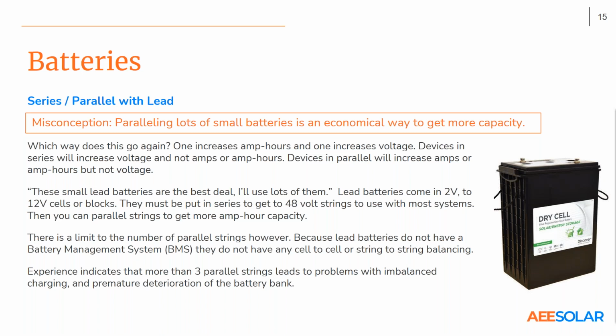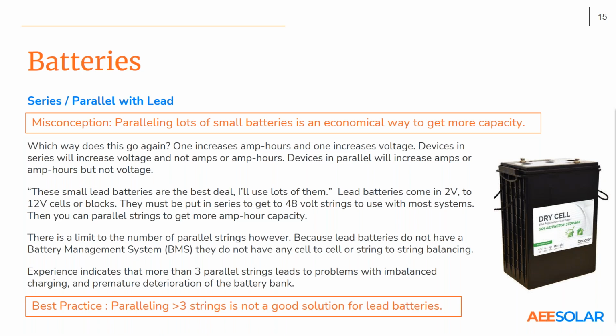So the rule of thumb is that with a lead battery, because they don't have a battery management system to do this balancing, you limit to 3 parallel strings. And one string is actually ideal. 2 strings is good, especially if you want some redundancy. If you have a bad cell, you still have half your battery bank. 3 parallel strings is okay most of the time. With flooded batteries, it can be a little bit of a problem. With AGM and gel batteries, it's not quite as much of a problem. Sometimes for just pure backup, UPS systems, you can go more. But for an off-grid system where you're cycling the batteries daily, 3 parallel strings really should be the limit.